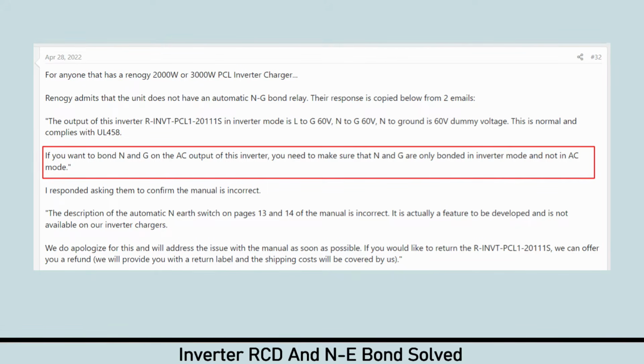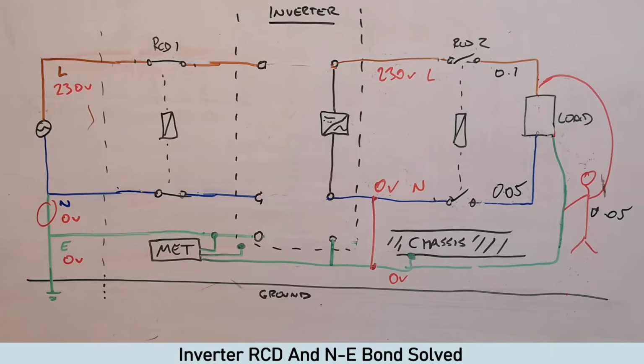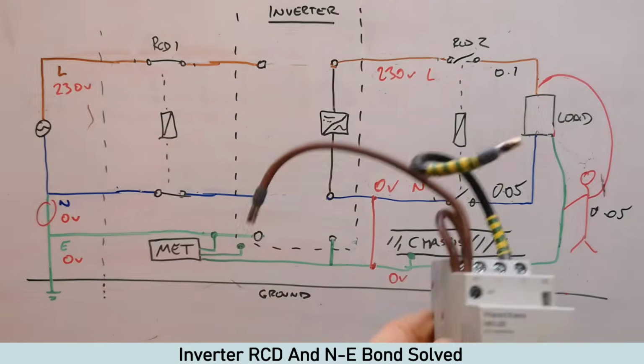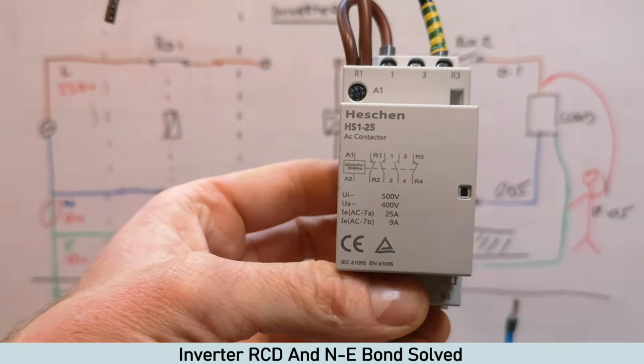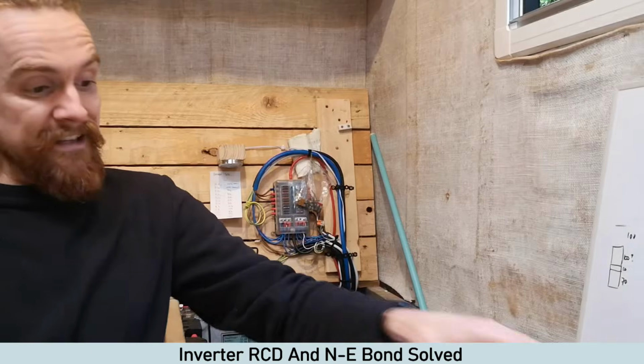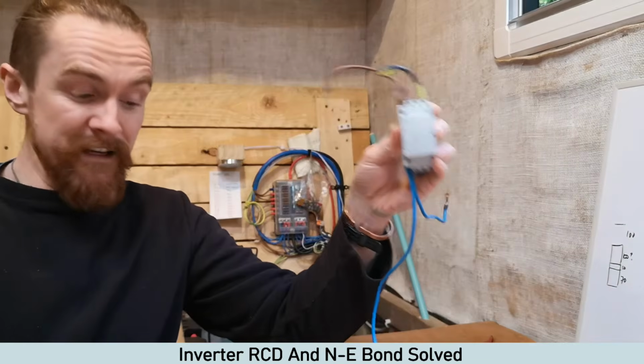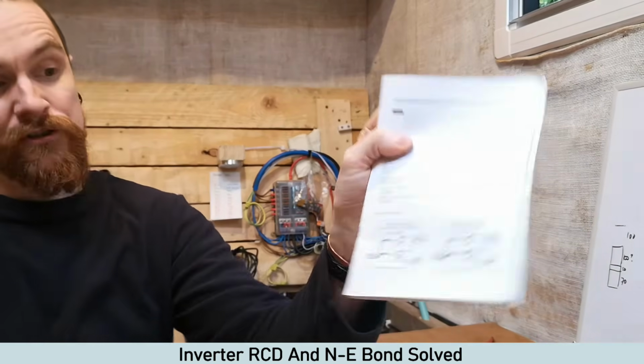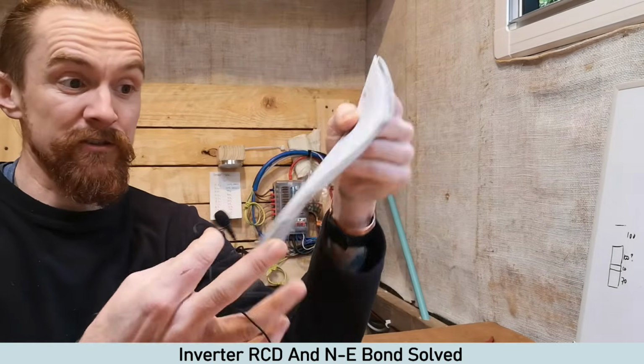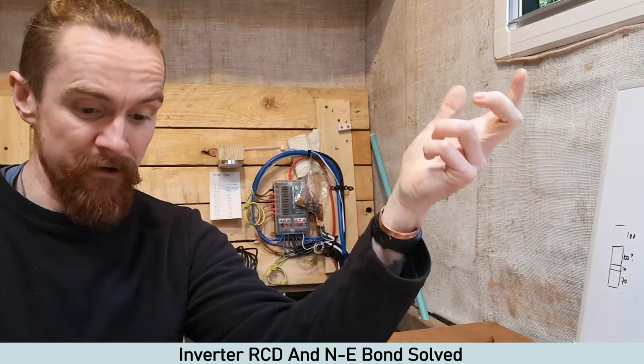So you can neutral to earth bond the inverter, but it must be removed when the charger is installed, like I've just shown you with the drawing. The only way to find out is to try, isn't it? So what I have is this. This is a contactor. What this contactor is, is basically what I've just shown you in the manual. It's just external, not internal.